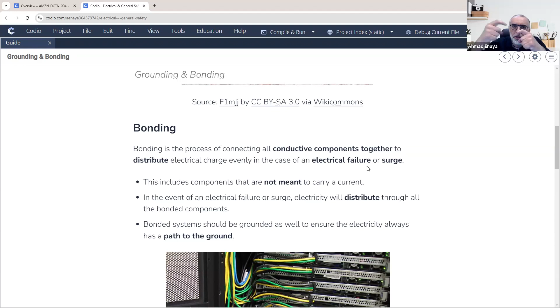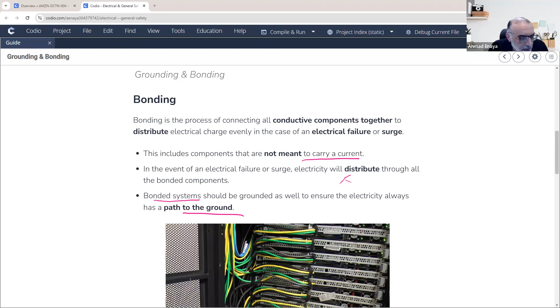And the bonding includes also devices that are not meant to carry current. Like what? Give me examples of devices. The floor, and also the rack, the cabinet, the rack door, the shelves in the cabinet. All these should be connected together. If they are all connected together, in case of failure, electricity will distribute through all these components. And then typically these bonded systems are at the end connected to the common ground of the building. So we have a common ground that makes all devices at the same potential level.